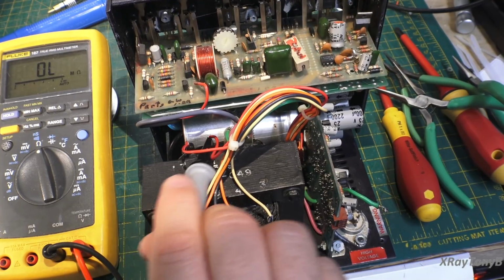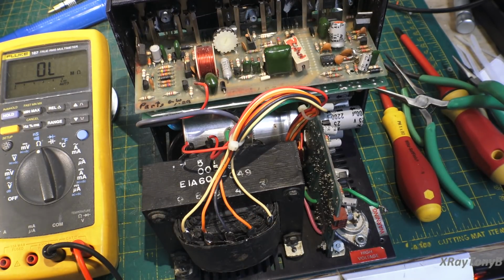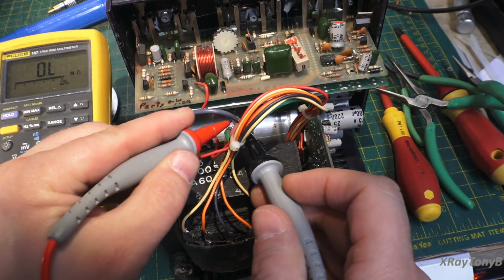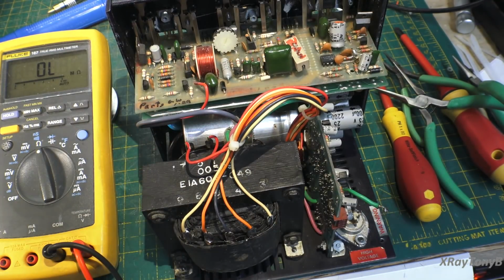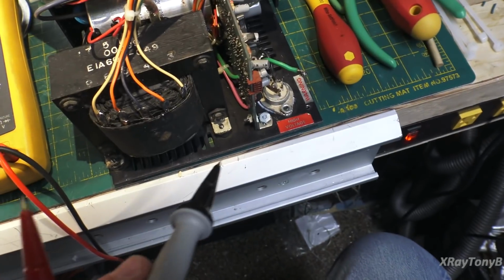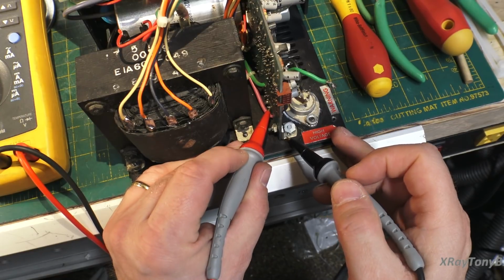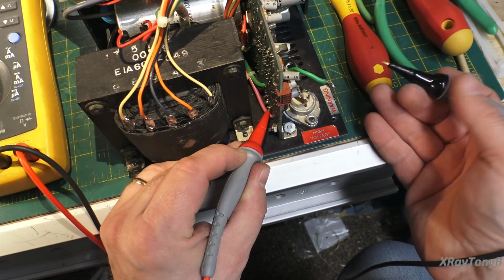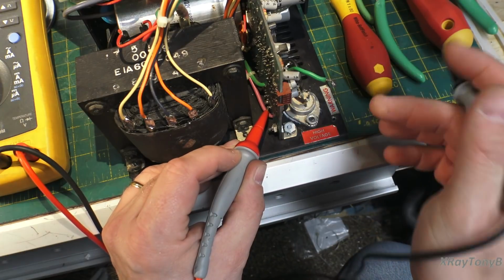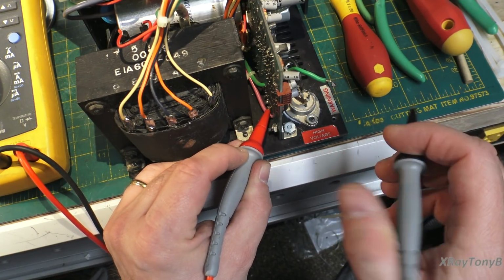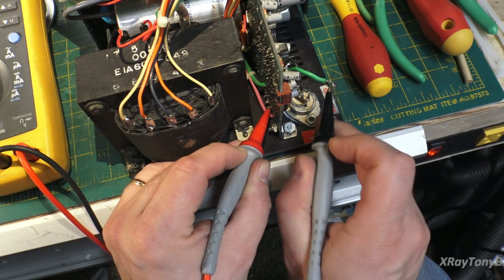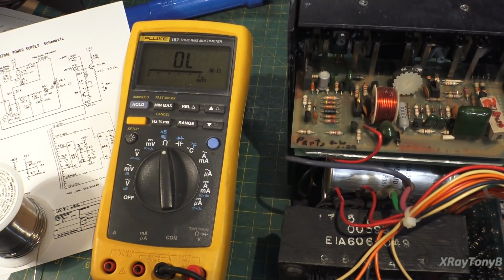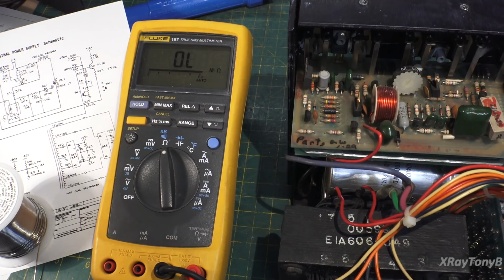Okay, I checked this one and it's good, so we put it back together. Now I'm going to check these ones. I don't want to take all this insulation off and redo that, but if you look, this pink wire on this side goes to this terminal right here, and the green wire goes to the triac, so I can just disconnect one leg from the triac and get my measurements right there. If I check right here, I'll show you—it's good, so far so good.